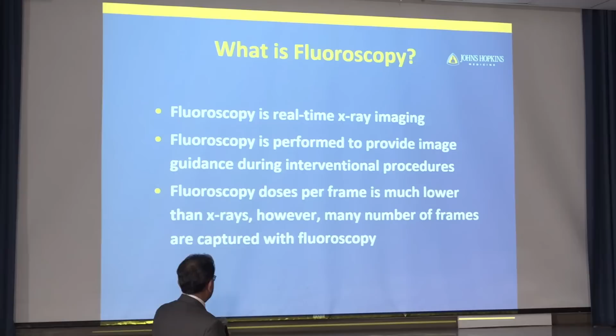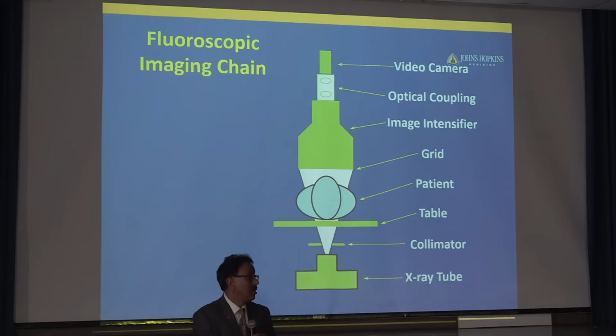This is a very fundamental drawing of the principles of fluoroscopy systems. Any type of system has an X-ray tube and a collimator. That's the part where the user can adjust the collimation, the field size, and there is a table and the patient, and there is a grid. The grid is basically a strip of lead septa to block a lot of the scatter radiation, and then there are all these boxes which capture the image, the X-ray signals, and convert them into an image and so forth. So these are the different types of fluoroscopy systems. Probably you have seen many of them.